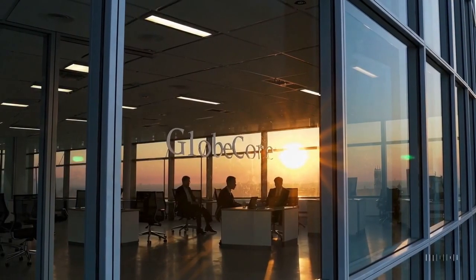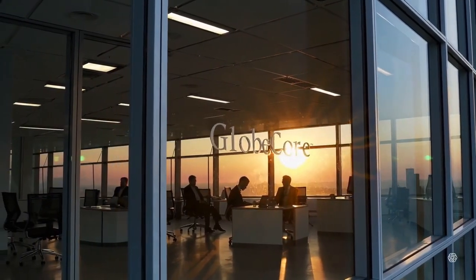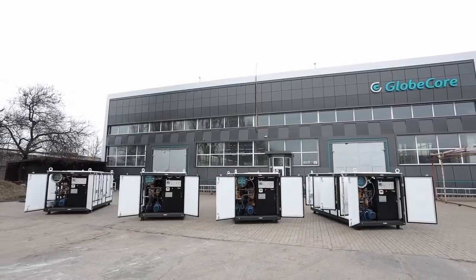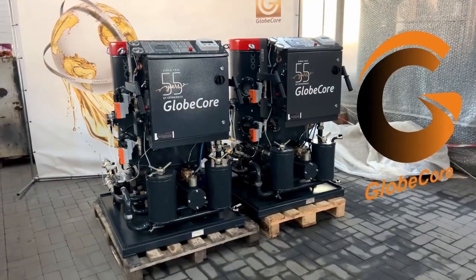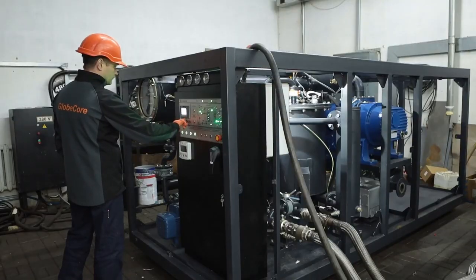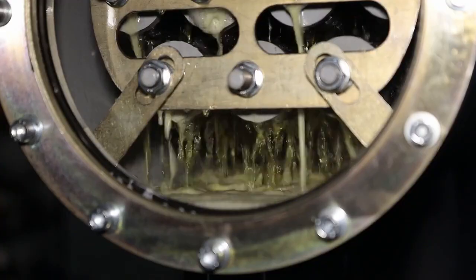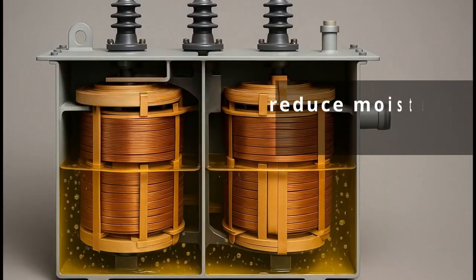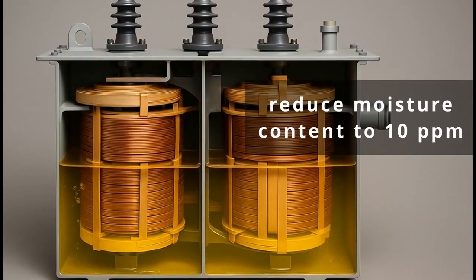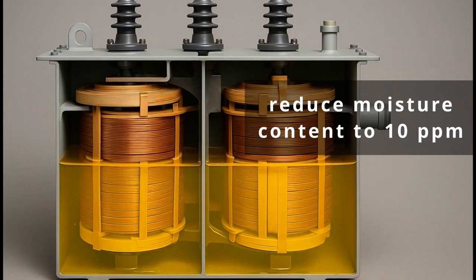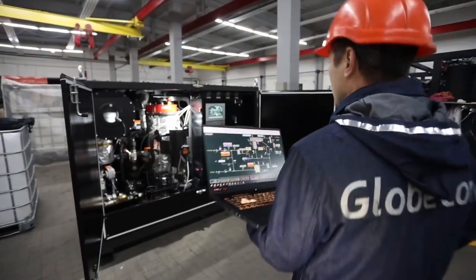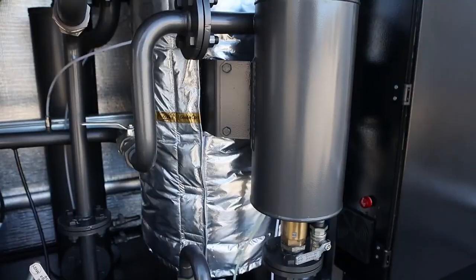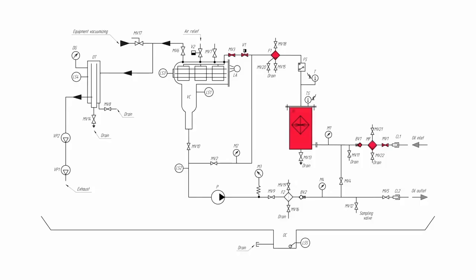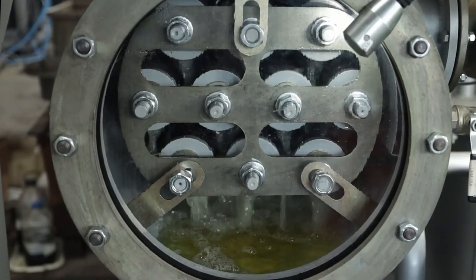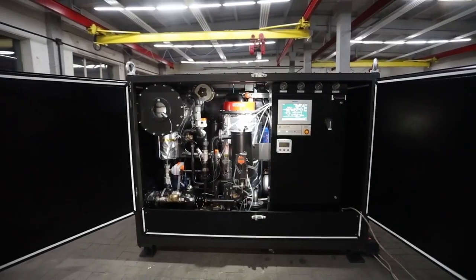GlobeCore specializes in the manufacture of CMM thermal vacuum machines for transformer oil purification and dehydration with a capacity ranging from 600 to 17,000 liters per hour. The typical GlobeCore technology allows reducing the moisture content down to 10 parts per million, which fully complies with most international standards. The process occurs in several stages. First, the oil flows through a heating unit, then enters a vacuum chamber, where moisture is removed from oil in the form of vapor. This is efficient, fast, and cost-effective.